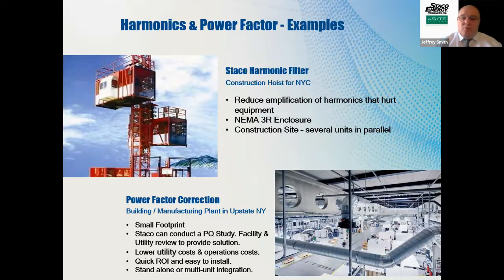It's amazing. We're doing some work in New York City, and the elevators and cranes building the buildings next door are causing so much harmonics being fed into the facility, and their power factor was so low that we installed a harmonic filter, as required, with power factor correction to adjust the power factor and give them better quality power in these facilities.